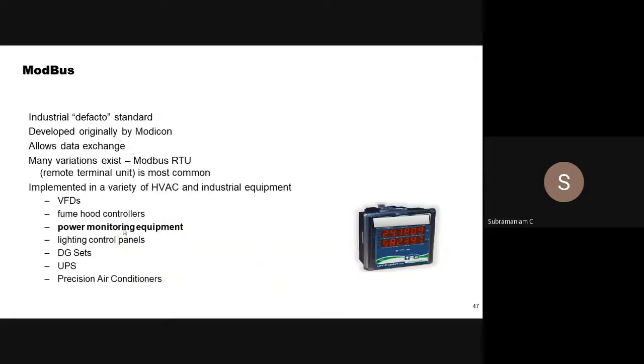Then Modbus is another protocol, which is a de facto standard for all major electrical equipment: VFDs, power monitoring, energy meters, transformers, DG sets, UPS, precision air conditioners, lighting control panels. By this, we can get the parameters. There are integrators available which will take this information on Modbus and convert it to BACnet, for the system level for us.